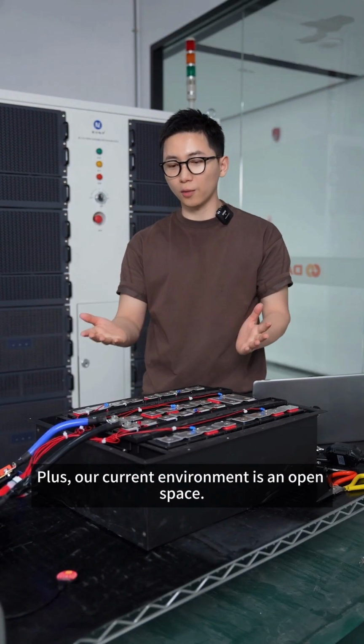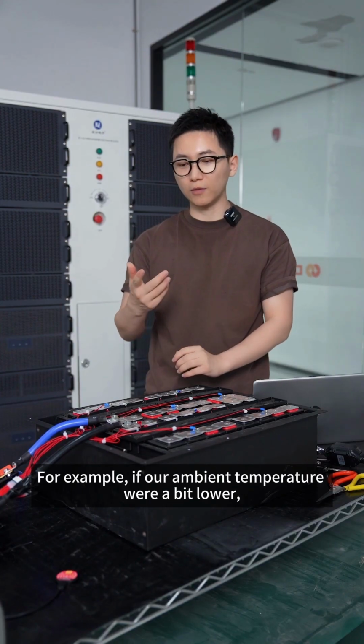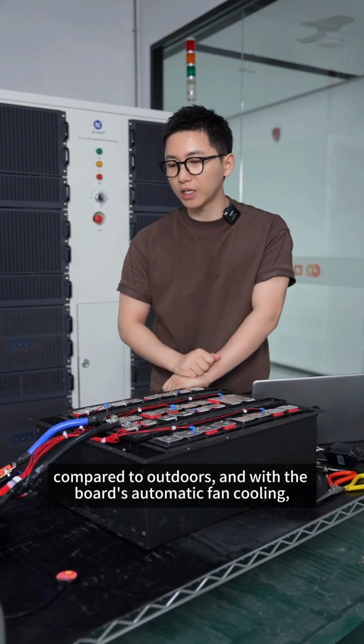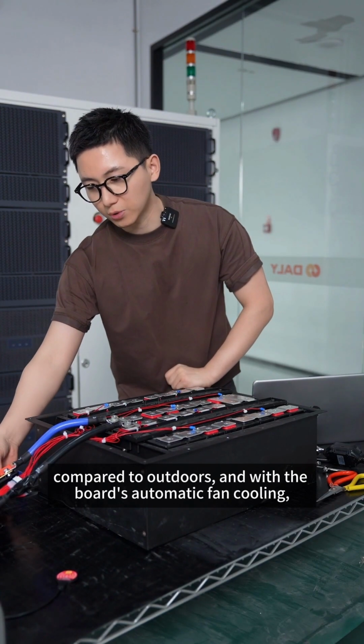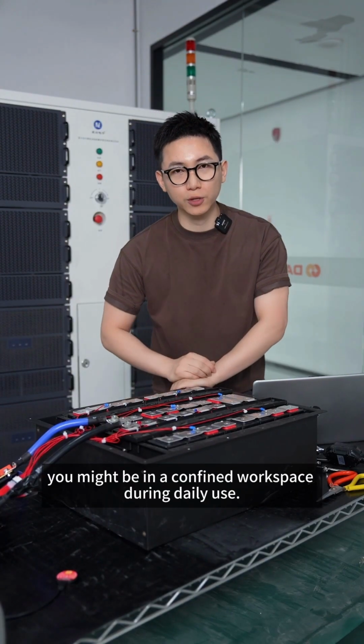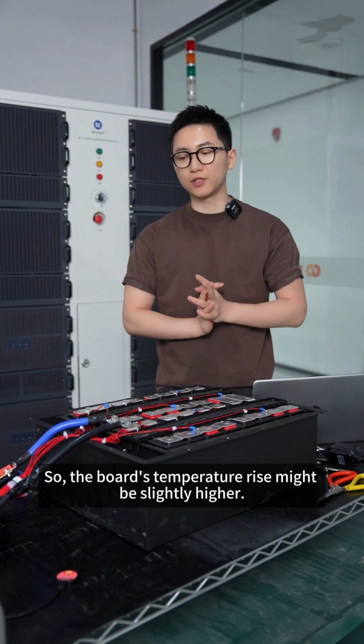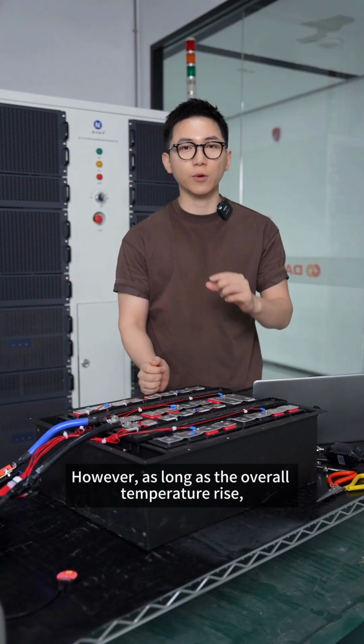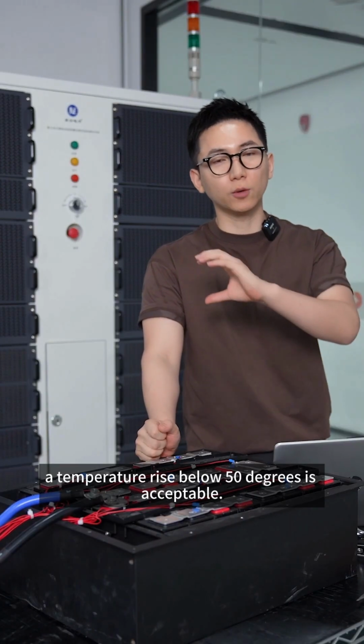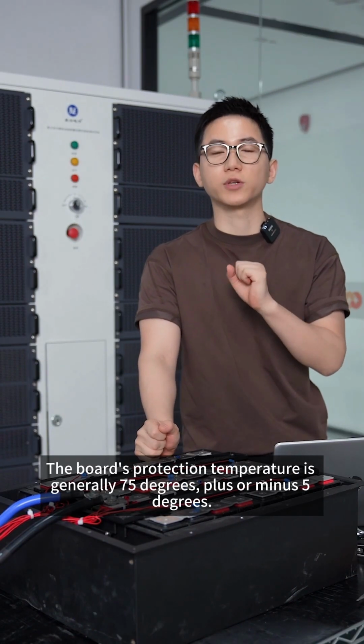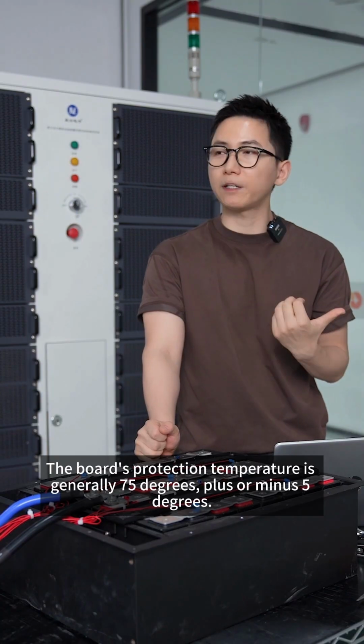Plus, our current environment is an open space. For example, if our ambient temperature were a bit lower compared to outdoors and with the board's automatic fan cooling, you might be in a confined workspace during daily use. So the board's temperature rise might be slightly higher. However, as long as the overall temperature rise is below 50 degrees, it is acceptable. The board's protection temperature is generally 75 degrees plus or minus 5 degrees.